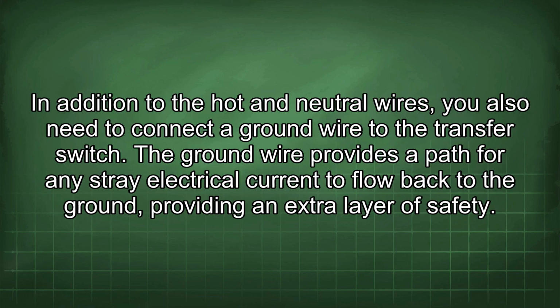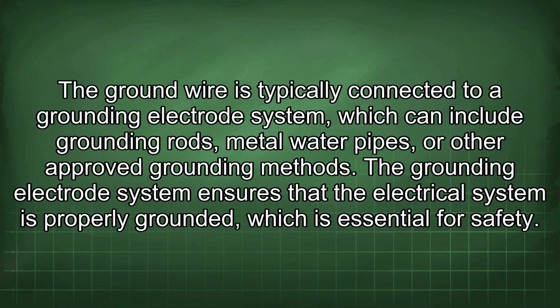In addition to the hot and neutral wires, you also need to connect a ground wire to the transfer switch. The ground wire provides a path for any stray electrical current to flow back to the ground, providing an extra layer of safety. The ground wire is typically connected to a grounding electrode system, which can include grounding rods, metal water pipes, or other approved grounding methods. The grounding electrode system ensures that the electrical system is properly grounded, which is essential for safety.